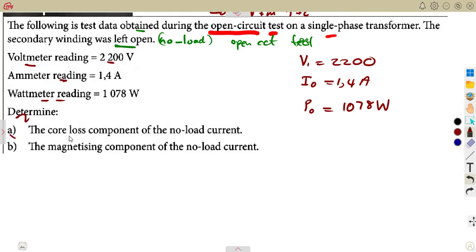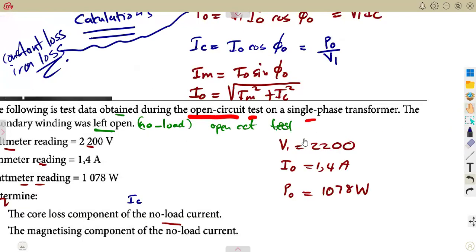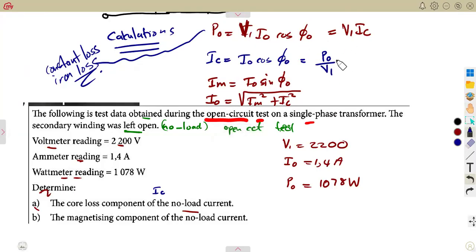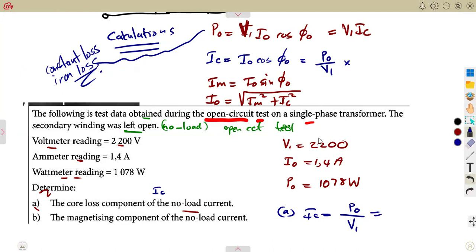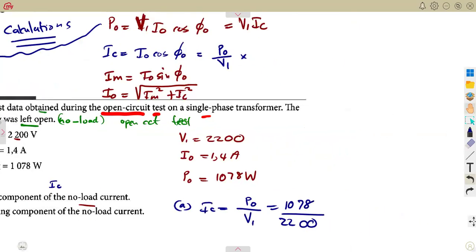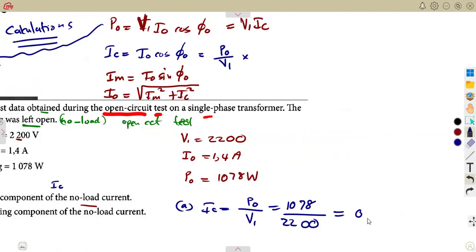Determine A: the core-loss component of no-load current. The core-loss component can be determined using the shorter formula: IC = P_noload / V1. The no-load power is 1,078 watts and V1 is 2,200 volts, so IC = 1,078 / 2,200, which gives us the core-loss component IC = 0.49 amps.